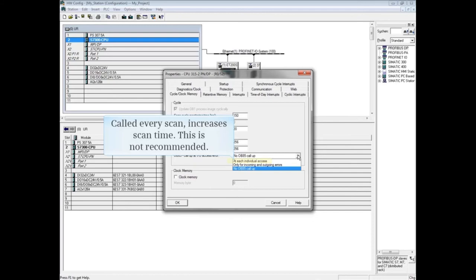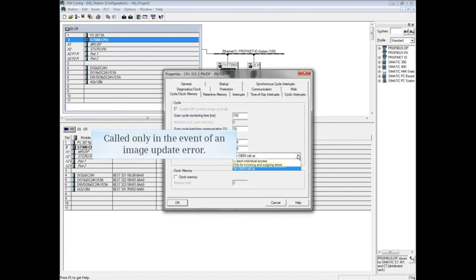This would increase the scan cycle time. Instead, choose 'only for incoming and outgoing errors.' Then OB85 will only be called if there's an error during the updating of the input and output images.